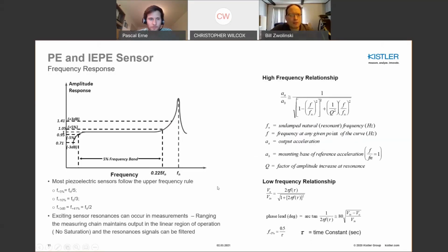In terms of the frequency response of a piezoelectric sensor, whether it's IEPE or PE, it's basically a single order high pass characteristic on the low end and a lightly damped second order characteristic on the high end. So if you make these assumptions and look at the frequency response, you can often tailor some closed form expressions, or at least approximations to amplitude response as a function of natural frequency.